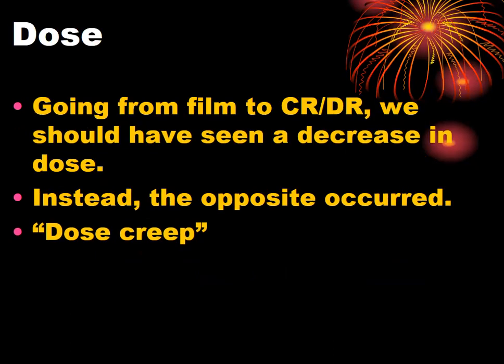When transitioning from film to CR and DR, patient dose should have decreased. Instead, dose creep occurred — mAs was pushed up because technologists didn't understand what the S number (exposure index) meant and didn't realize they were overexposing patients. Early equipment representatives even encouraged technologists to increase mAs by 25–50%. As a result, instead of using less technique, more was used — and the images looked great at high mAs, reinforcing the bad habit.